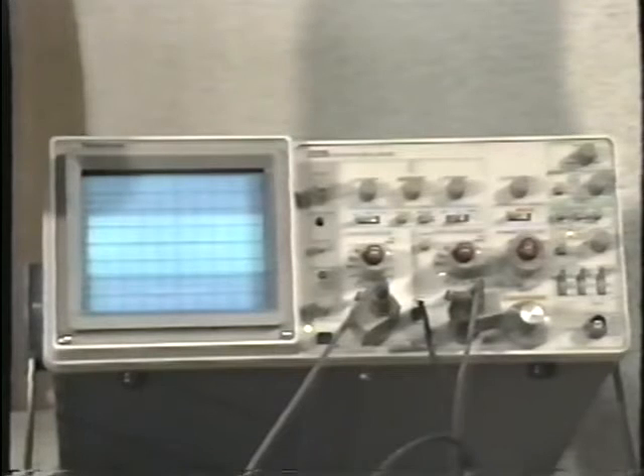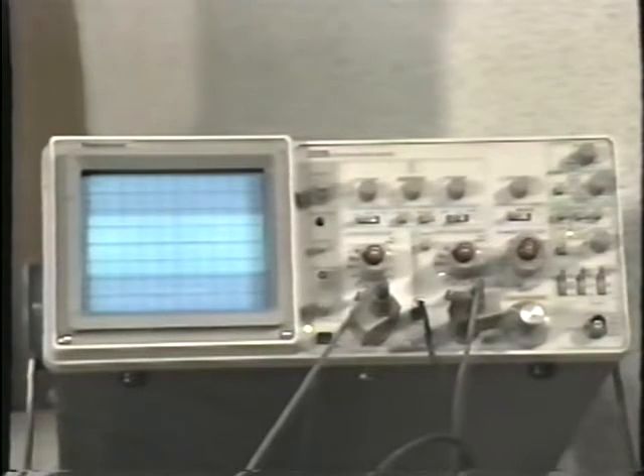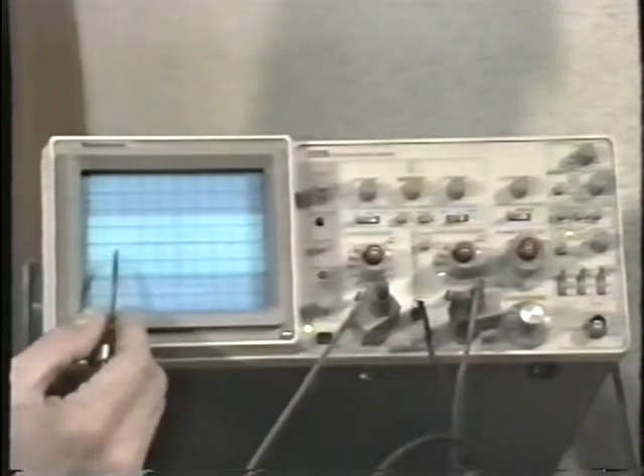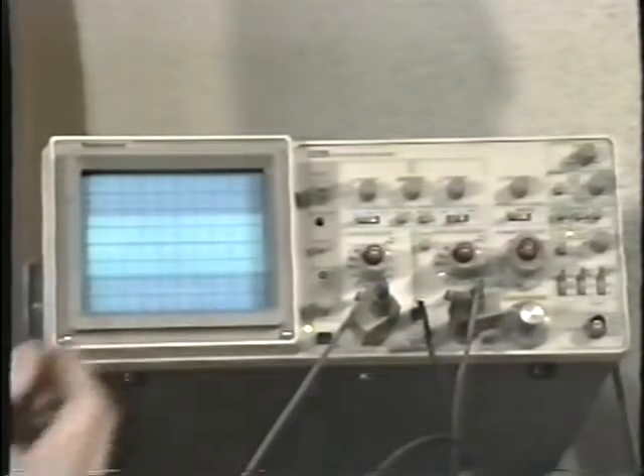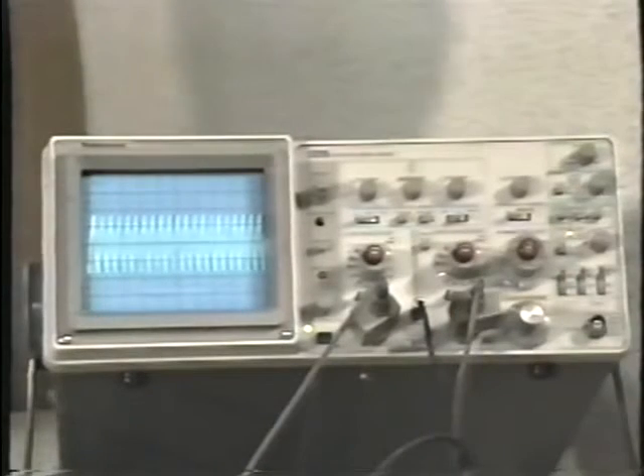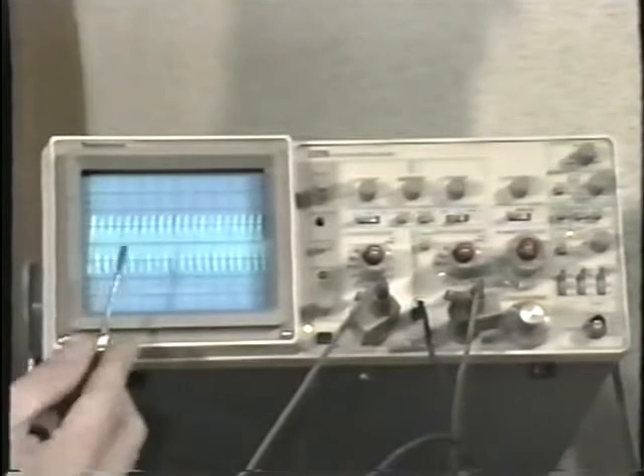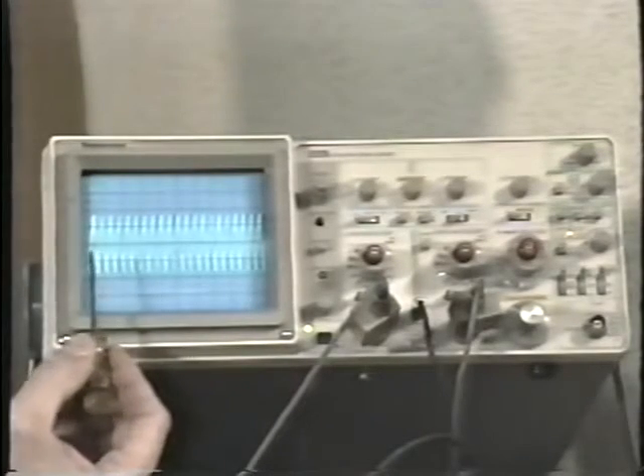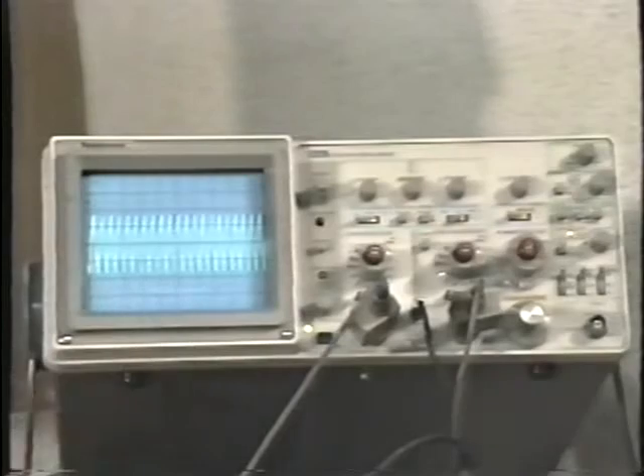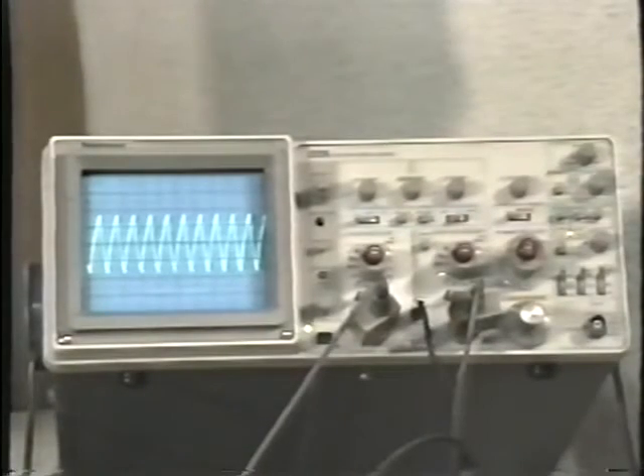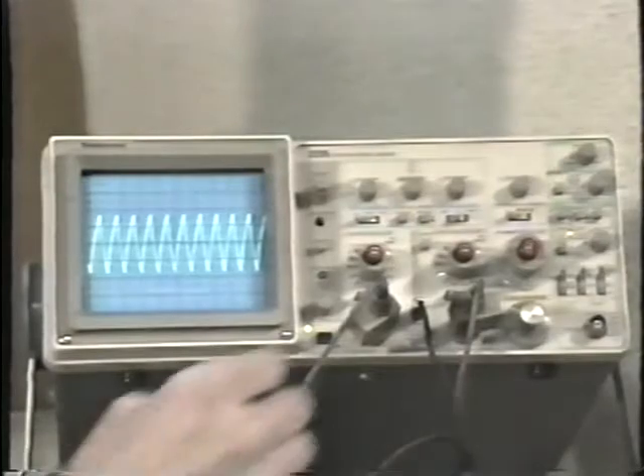There's a 1/2 millisecond per division, 0.5 milliseconds per division, and I'm starting to see the individual peaks that make up the waveform. Next step, 0.2 milliseconds per division. Again, the sequence is 5-2-1. Here we're on 0.2, or 2/10 of a millisecond, for each division. There's 1/10 of a millisecond per division. And we can clearly see the waveform that's being generated by the pattern generator.